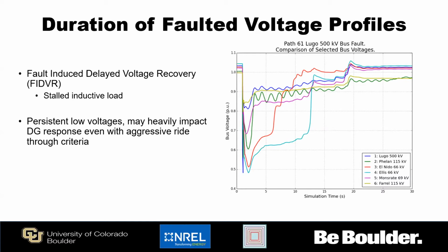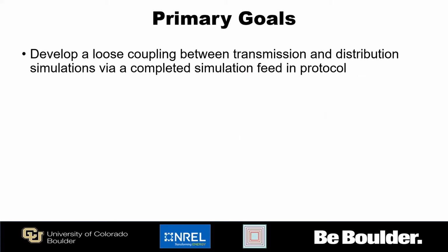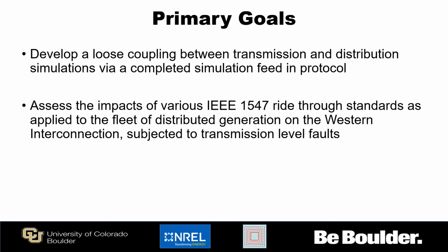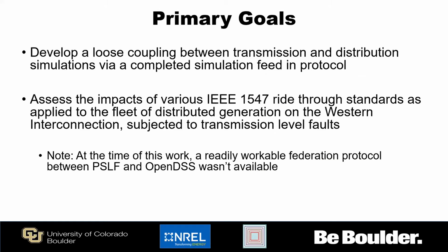So that's far beyond most of the ride-through capabilities and requirements of the distributed generation. So even though we have these new requirements, some of the events can actually exceed those and then give us potential issues for reliability. And so the primary goals of this study were to be able to couple a transmission level simulation with a distribution simulation so that we can assess the impacts of some of these different IEEE 1547 ride-through standards and look at the impact of them on the Western interconnection of the United States during fault events.